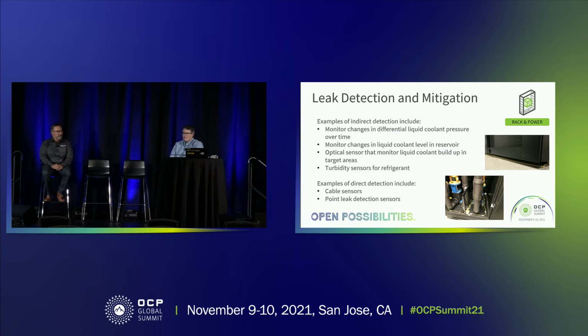I think that really illustrates the system design aspect. With a refrigerant base, you're not using a conductive means of sensing leaks, but there are different tools depending on the different fluids used, and the same with dielectrics. When you factor in two-phase dielectrics where you have that phase change, that's another consideration.